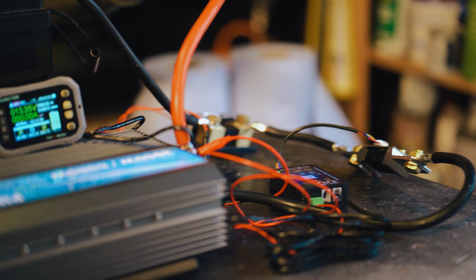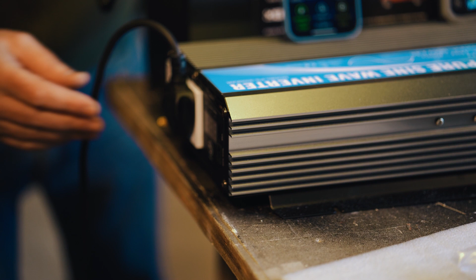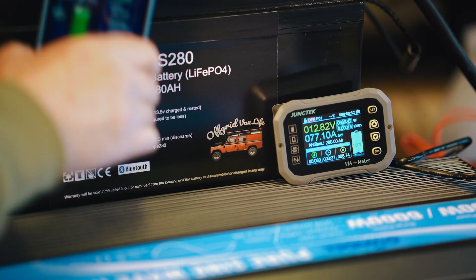We've fully connected the Giandel 3 kilowatt inverter through all the way. We have a little heater at the bottom here. We're going to turn this on. The inverter is saying 13.4 volts, which is about correct. And straight away you can see we've gone to 77 amps on here, 77 amps.